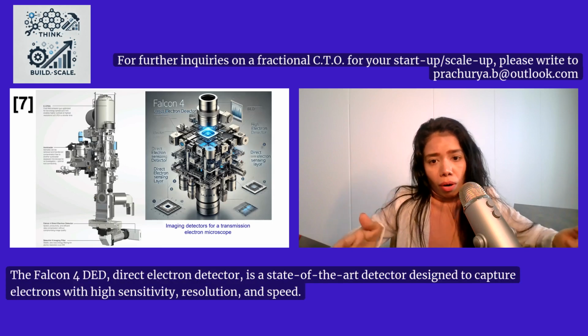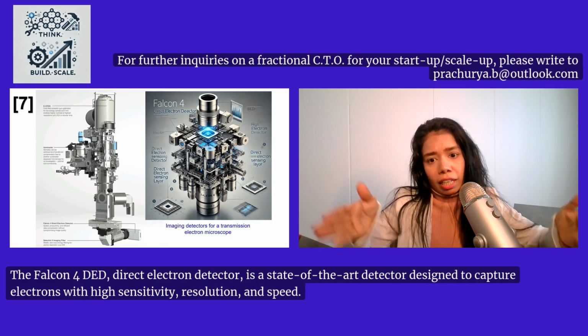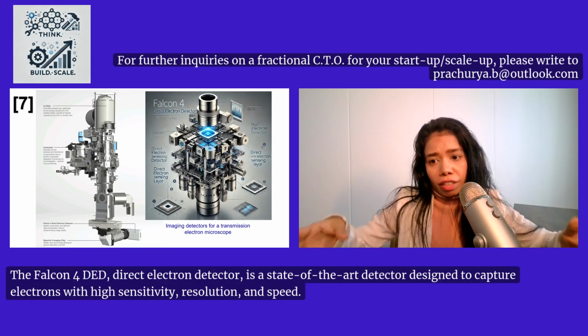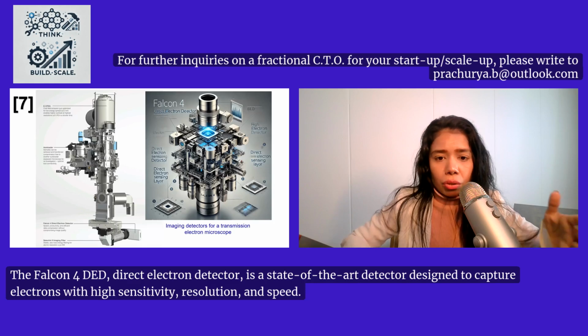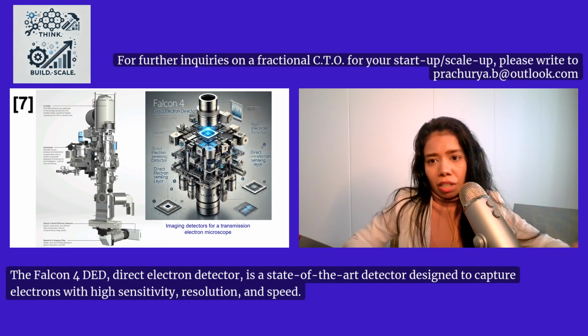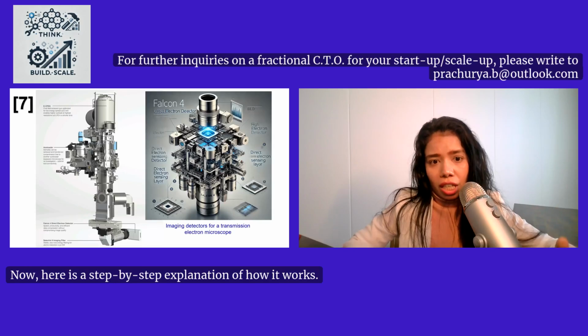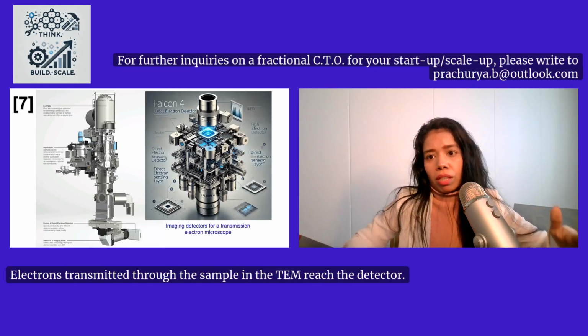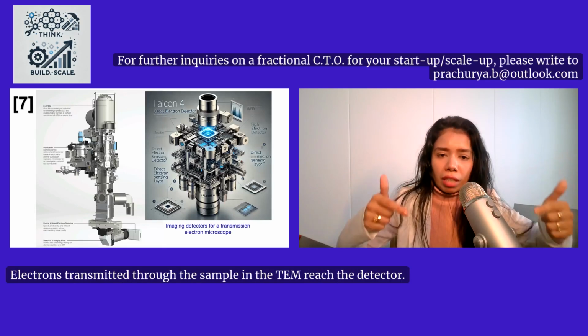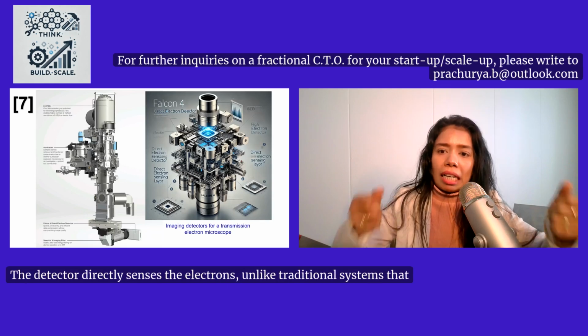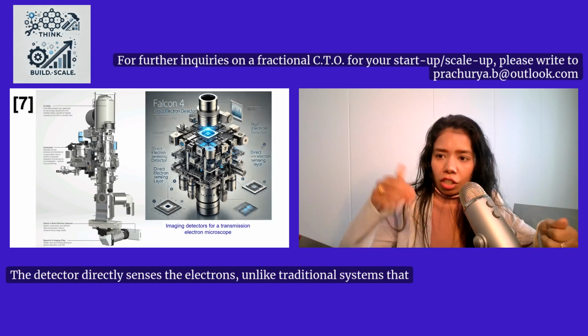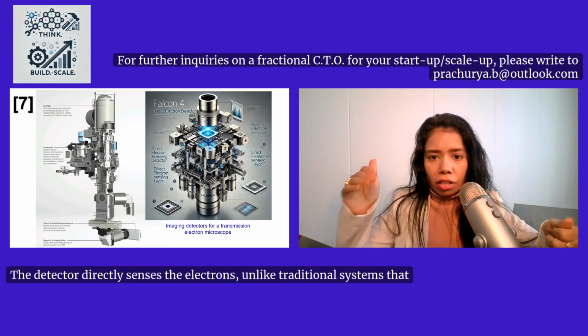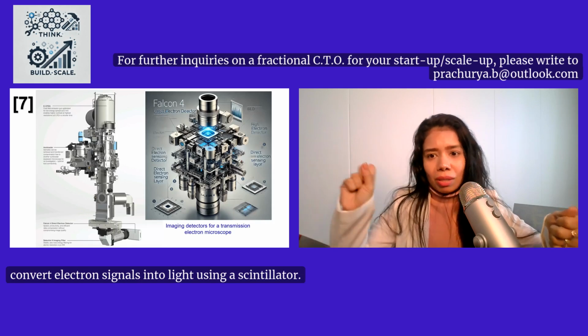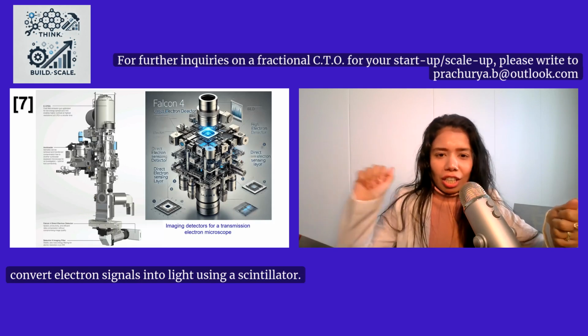The Falcon 4 DED, direct electron detector, is a state-of-the-art detector designed to capture electrons with high sensitivity, resolution, and speed. Now, here is a step-by-step explanation of how it works. Electrons transmitted through the sample in the TEM reach the detector. The detector directly senses the electrons, unlike traditional systems that convert electron signals into light using a scintillator.